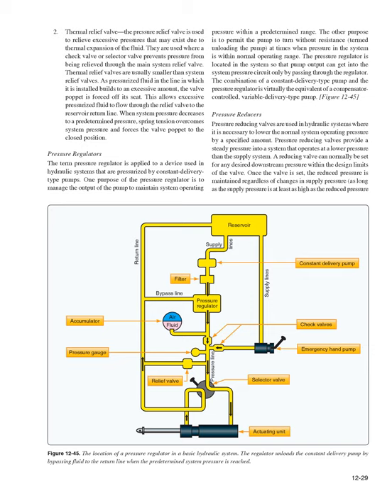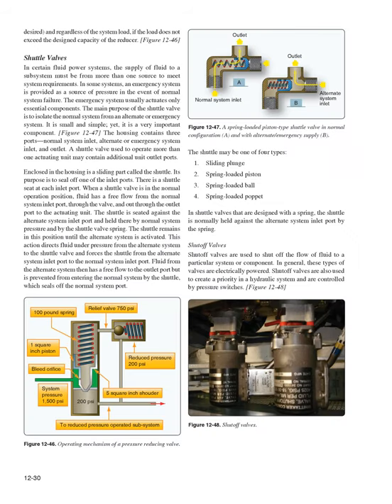Pressure reducers. Pressure reducing valves are used in hydraulic systems where it is necessary to lower the normal system operating pressure by a specified amount. Pressure reducing valves provide a steady pressure into a system that operates at a lower pressure than the supply system. A reducing valve can normally be set for any desired downstream pressure within the design limits of the valve. Once the valve is set, the reduced pressure is maintained regardless of changes in supply pressure, as long as the supply pressure is at least as high as the reduced pressure desired, and regardless of the system load, if the load does not exceed the design capacity of the reducer.